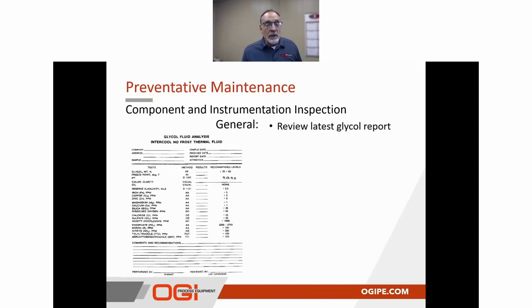In general terms on that component inspection, we also want to take a look at the condition of the glycol that's in the bath. So in this case, the first step we want to do is take a look at the latest glycol report to confirm that the glycol samples have been drawn and that the bath chemicals have been corrected. In this case, let's say a year ago that samples were taken, we want to make sure that there's a documented path that says, okay, we found something that was low and that it was treated to bring that pH or that inhibitor level to the right level, and that the glycol was made back to a good form.